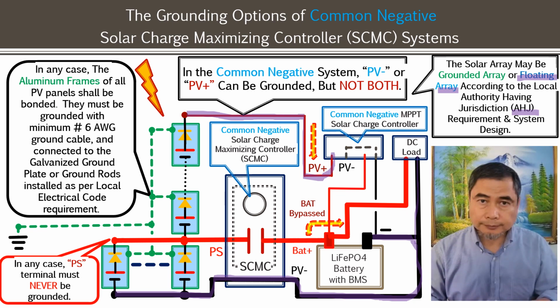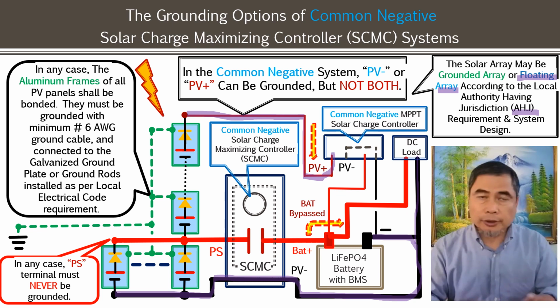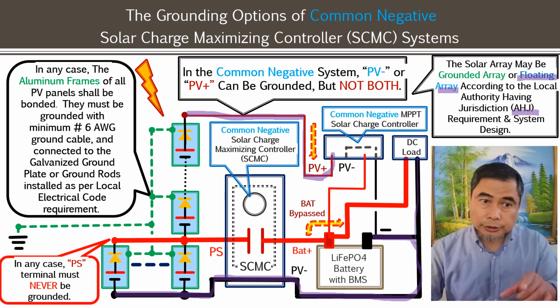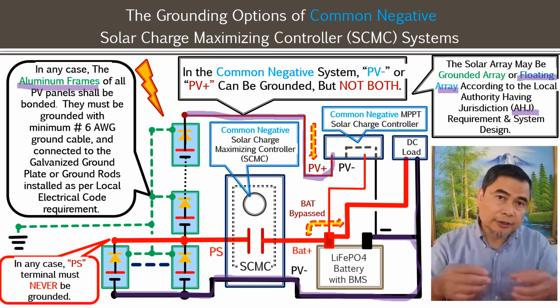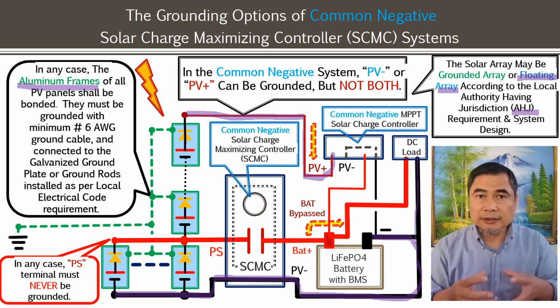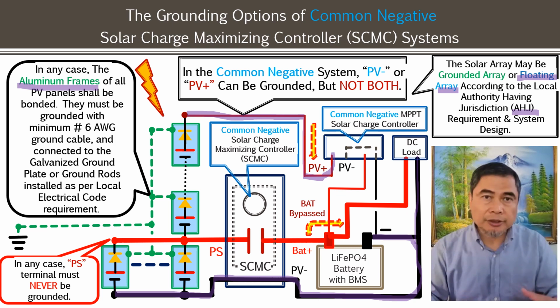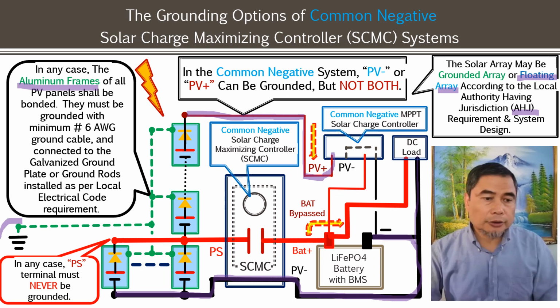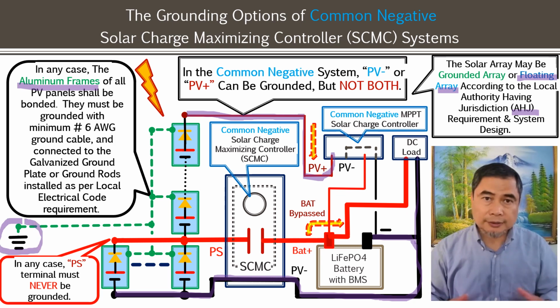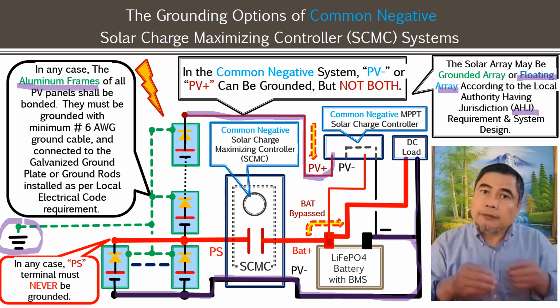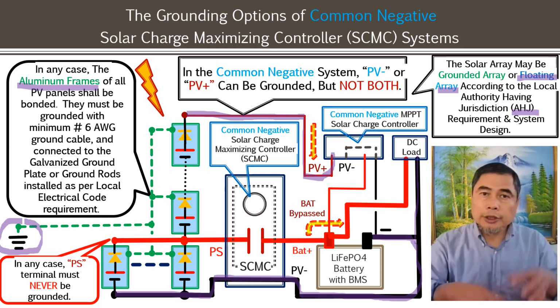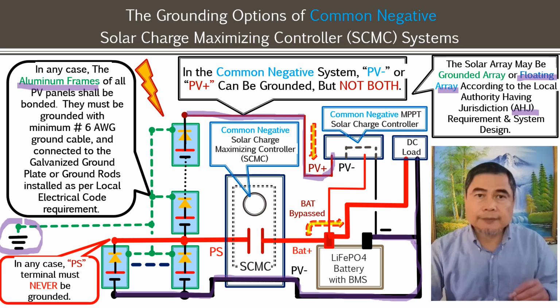However, regardless of whether it's a floating design or a grounded solar array, one thing is for certain: the aluminum frame, the solar panel aluminum frame. On the solar panel side, you always have small holes designed for you to fasten the panel down, and also to connect the ground cable to the ground. You would normally design a system with the grounding very close to the solar array where you install those panels, because this is very important.